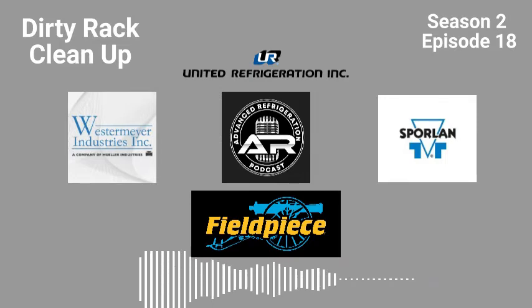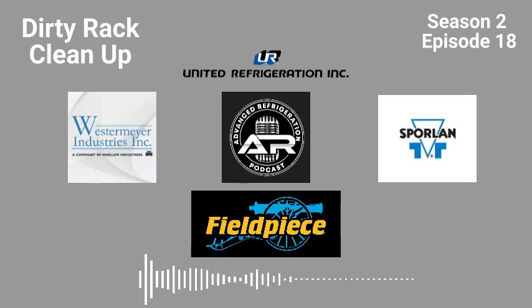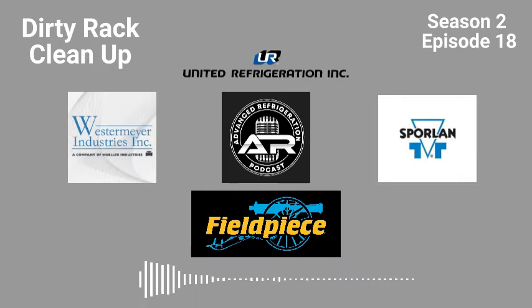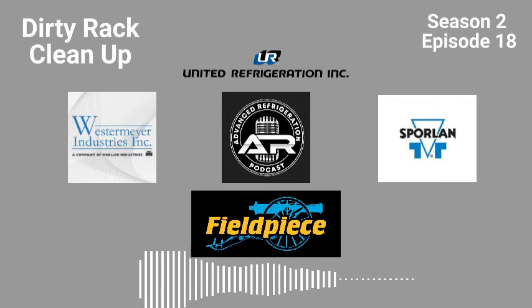But yeah, dryers in the cases. Dryers in the cases make the problem worse because they start plugging up over time, you lose performance, and then they lead to more rack issues, more overheating. Especially if you have something plugging, say a case that's running warm, one case in the lineup, don't just do the one case, do the whole lineup. Cut all the dryers out of the entire lineup or change all of them, because if one's plugged, I guarantee you the other ones are not far behind.